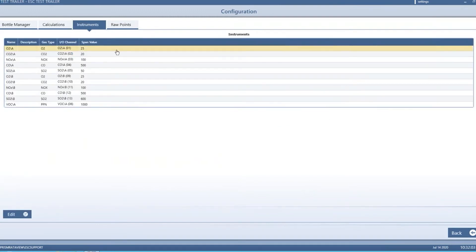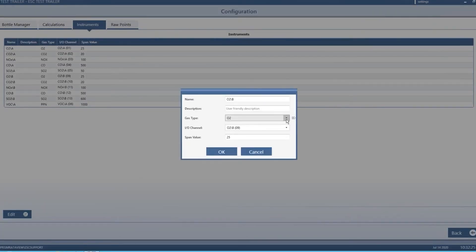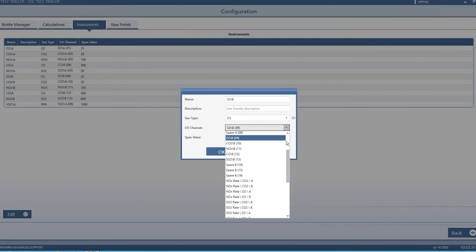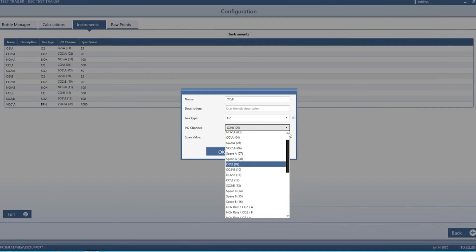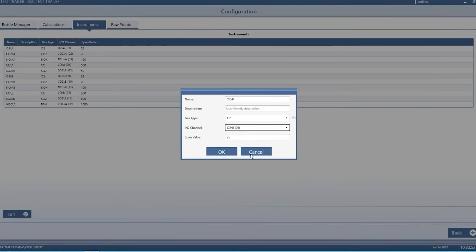Here are the instruments configured for this system. You can see the A bank and B bank of analyzers, the gas type they measure, the IO channel they're on, and their actual span value. You can edit each one. By clicking on it and hitting edit, you can change the gas type. If you need to switch your O2 analyzer with your CO2 analyzer, you can do that here. You can change the input channel and the span value as well. We have a couple spare channels visible here, so if you blow a channel, you can move the wires over and reconfigure accordingly.